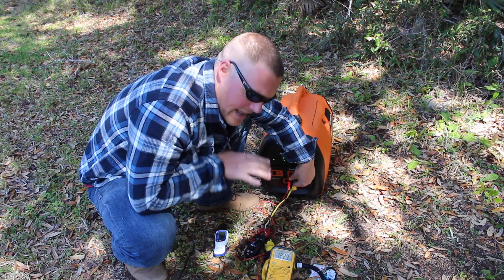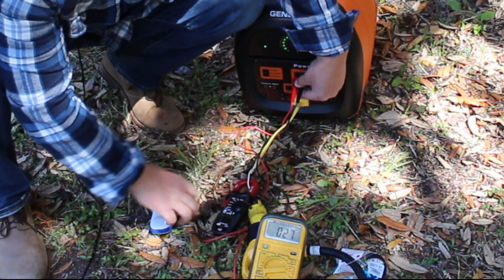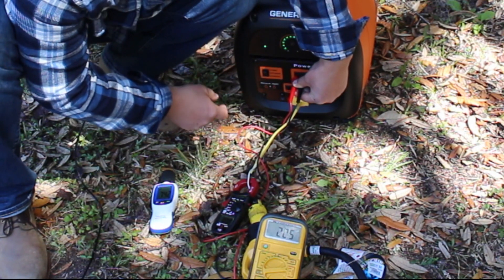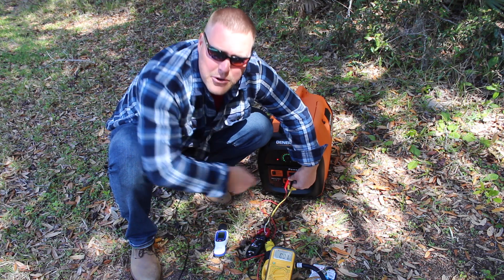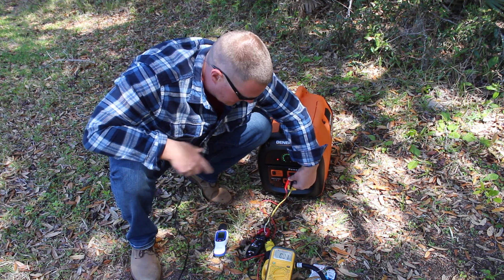It was a little shaky there. Now we're going to wait for that time delay when that compressor kicks on. 3.5 amps. There it goes. That's it — threw a breaker. So it wouldn't run it. It didn't even rev up.